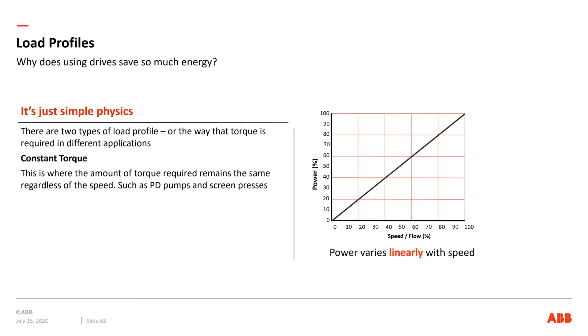And it's directly proportional. You do have some energy savings and less wear and tear, but you also have less load, so when you're running at half speed, you're only producing half of the flow that you would get on a constant torque. But your power is linear with speed. It's a direct relationship. Go to the next slide, please.